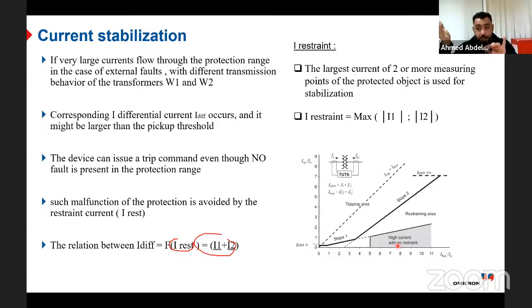The restraint current. So the relay will detect that the restraint current is increasing at the beginning, and after a certain number of cycles, the differential current starts to increase. So it means there is an external fault plus a saturation. Because if the fault is internal, both of them will increase simultaneously, the differential current and the restraint current. So the relay will understand that in this case the fault is internal, because both of them start increasing together.